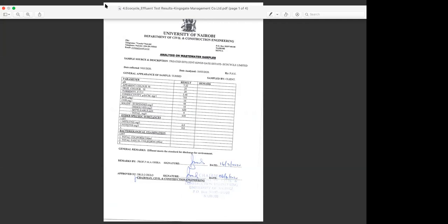When we develop, you saw the reactor chamber, where we grow the biomass, and that's where the treatment happens. When our biomass film has developed to maximum, during sedimentation or settling, when we do not have aeration, it acts as a perfect blanket and goes down with all the sediments, so that the water that is left has no floating substances or particles that are visible. So by the time it's going to storage, it's usually very clear and almost can be confused with drinking water. The only time we are likely to have issues is in case we get power outages or a client forgets to pump out the treated water, and so there is a mix-up. So some clients take that precaution.